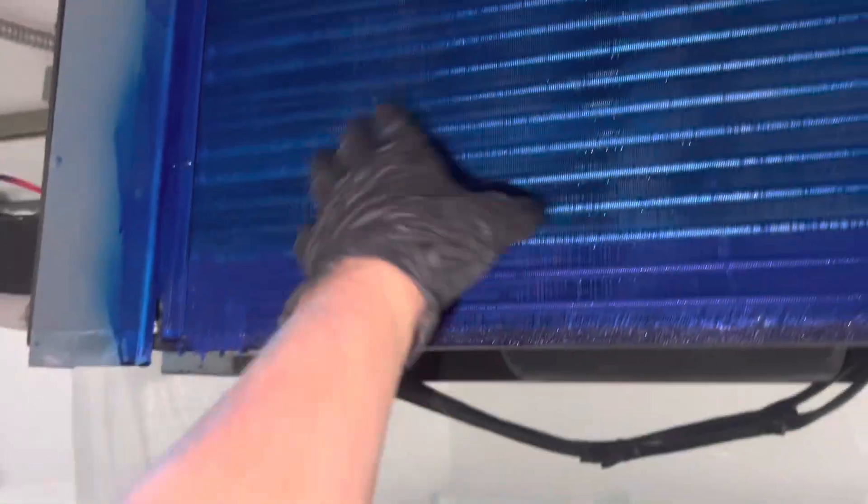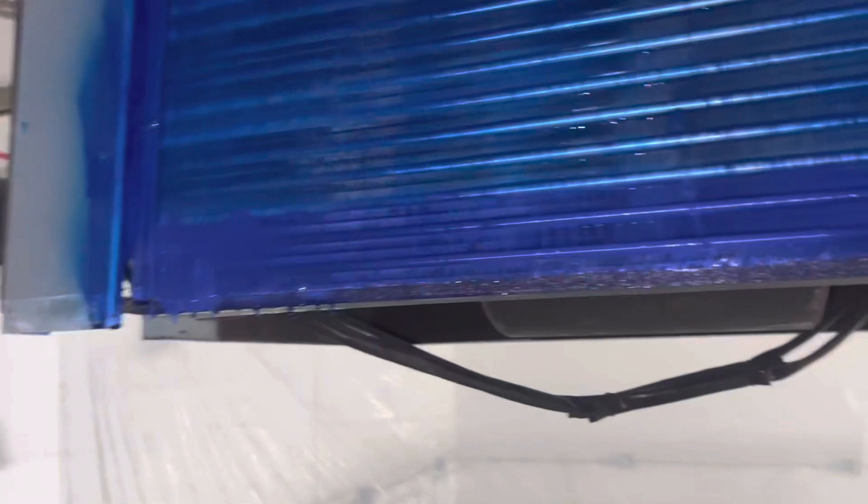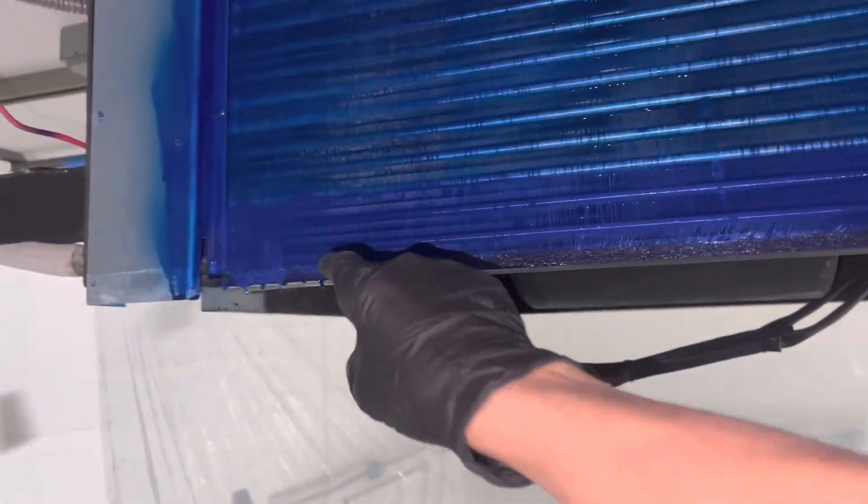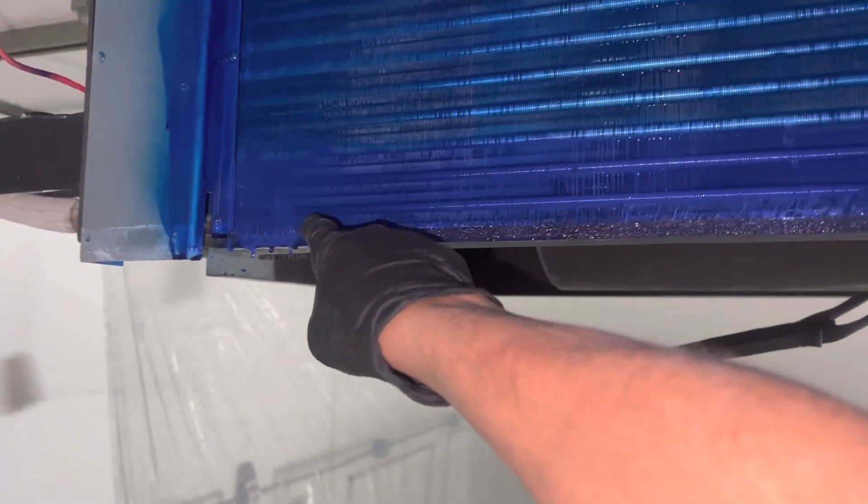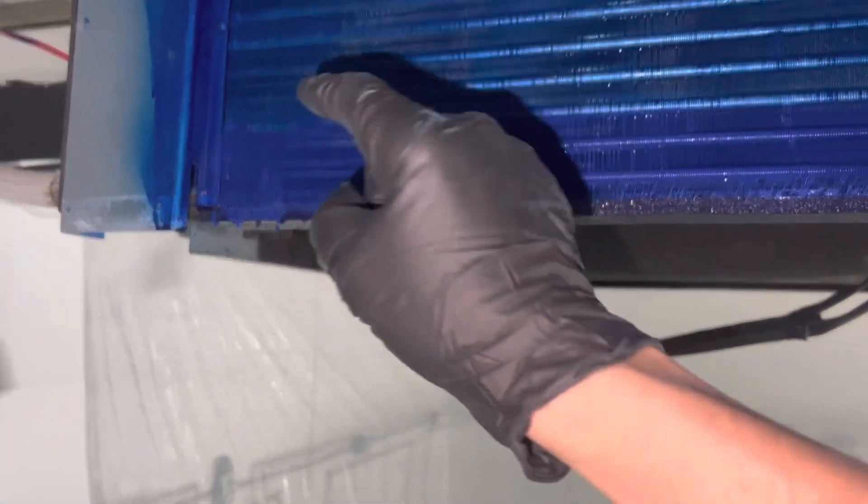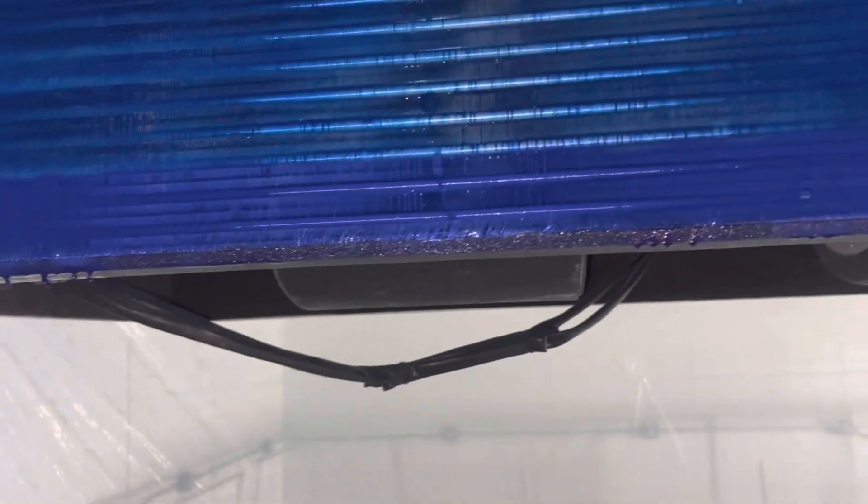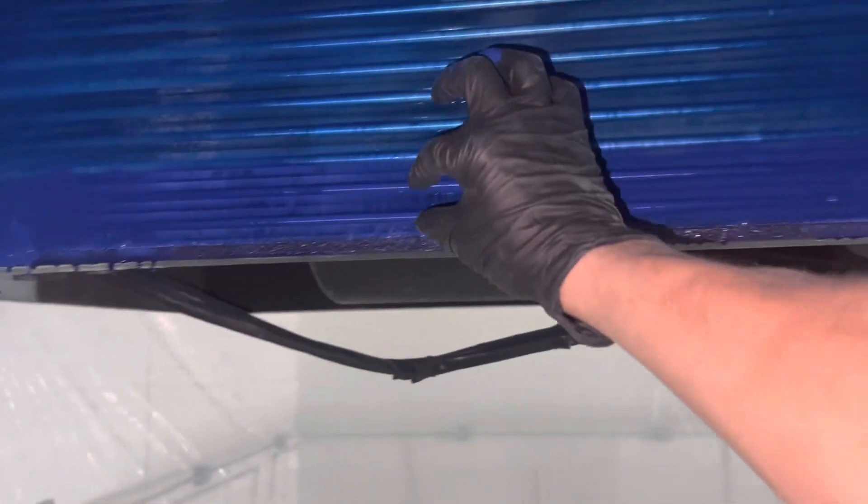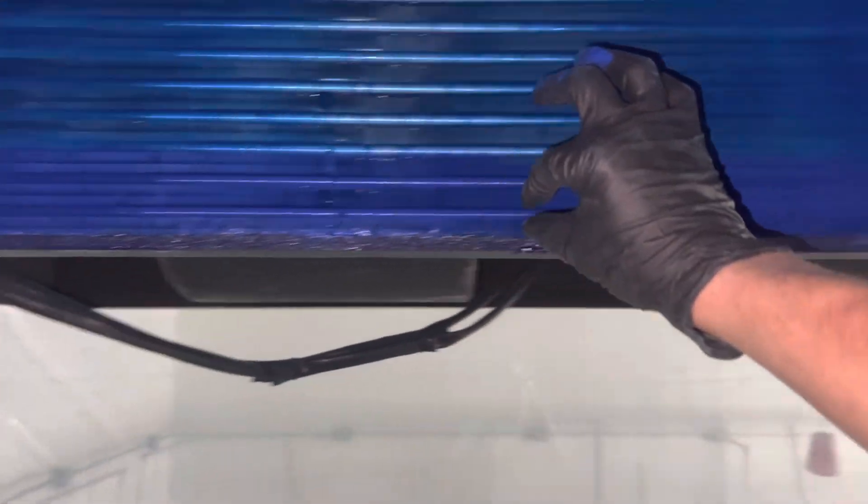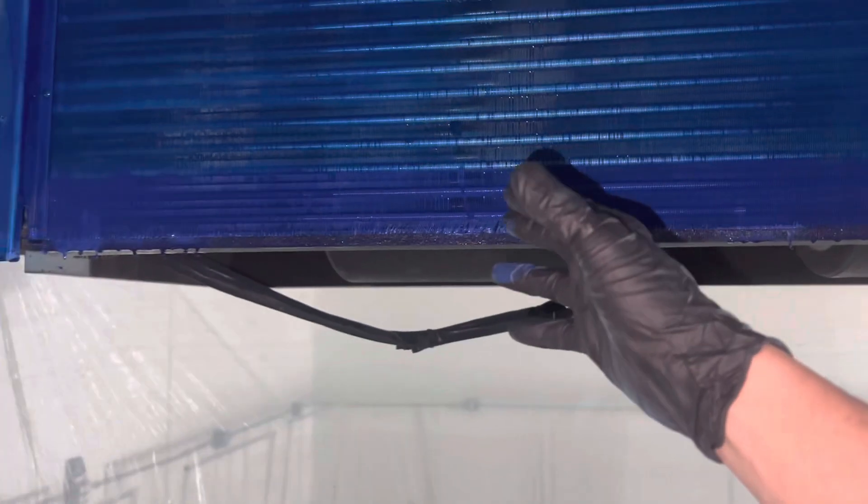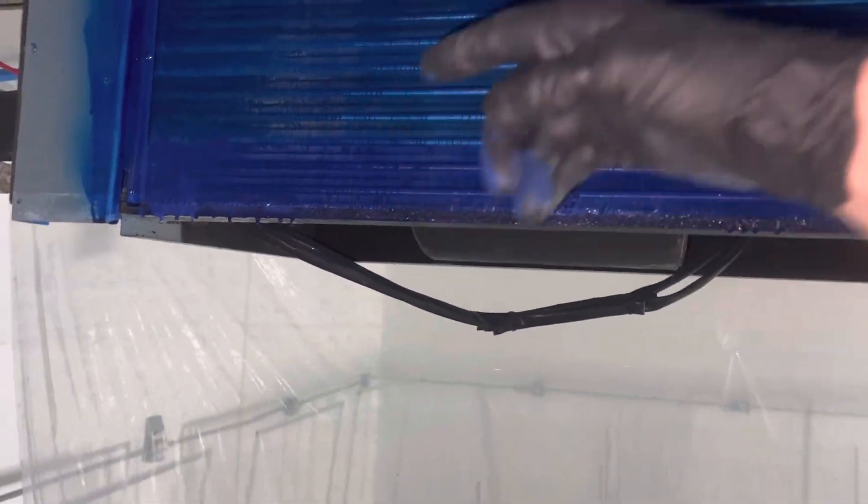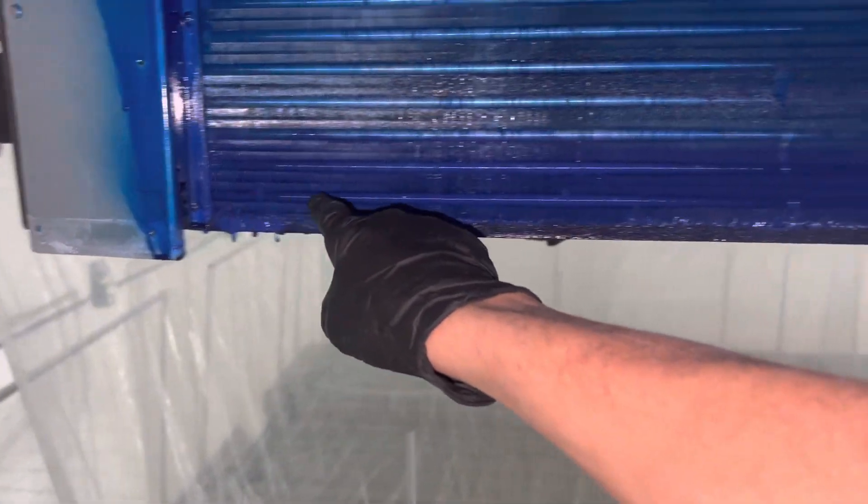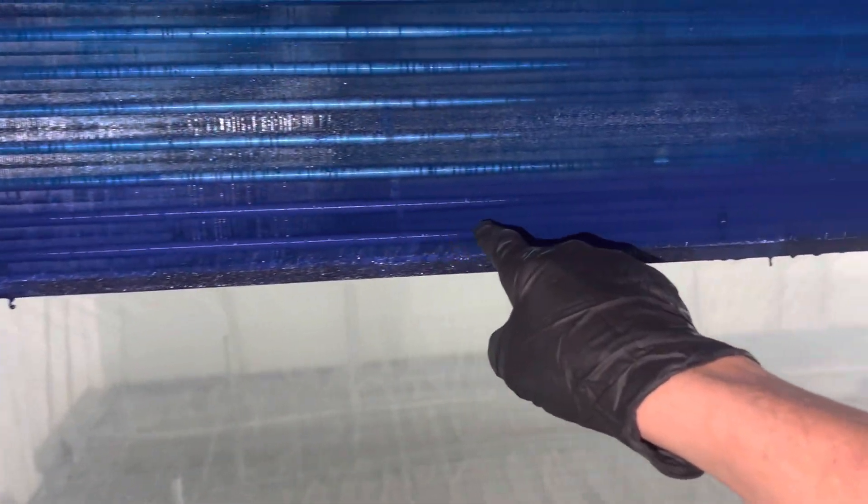Where we always find the leaks is usually the bottom coil, the very bottom coil, and so I have extra heavy coating right there. This will go overnight—we'll put it in heating mode in the next couple hours. This has been sitting overnight, but this morning I hit it with one final coat on this last row right down here.